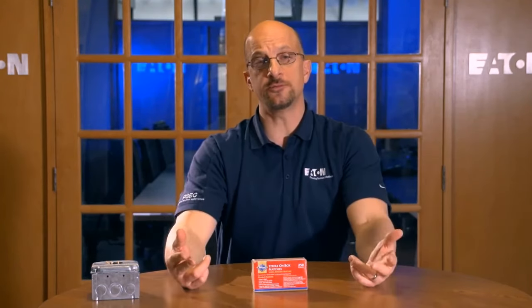Similar to an arc flash event, if we can control the time and distance of the arc flash, we can lessen the impact. Here at the Experience Center, we can show you options that reduce the time of the arc flash event and increase the distance of the worker to the location where the arc flash occurs.